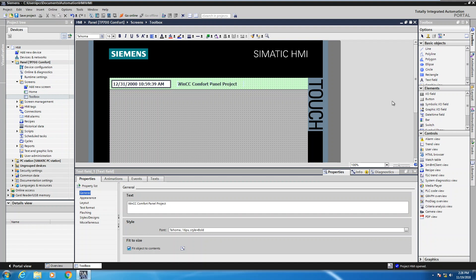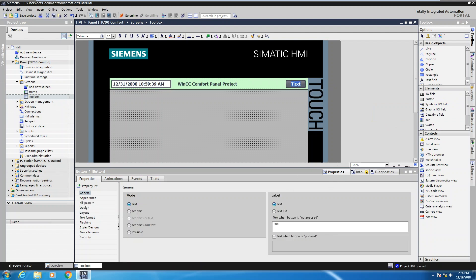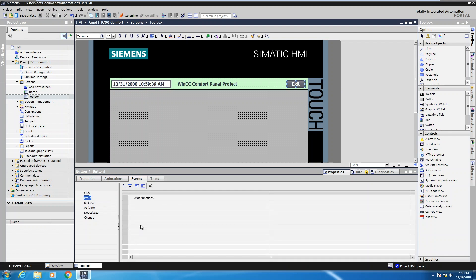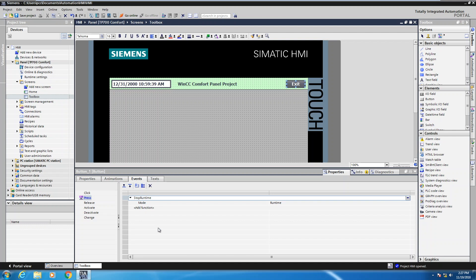I'd also like to put a button on my screen that will allow me to exit the application. Under elements I'm going to take a regular button object and draw it onto the screen. The text is already highlighted so I can type in a title — this is going to be an exit button. Once the button is selected I'll select the events tab and the press event. There is a function called 'stop runtime,' so in the add function area I can start typing 'stop' and IntelliSense will expose the stop runtime function. I'll select that function, so now when we press the exit button during runtime it will shut down the runtime system on the HMI.